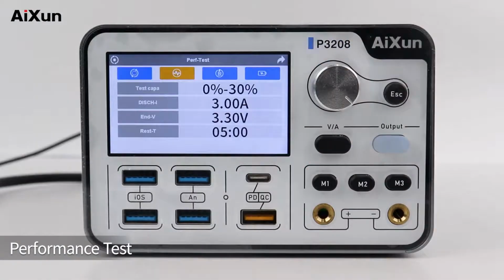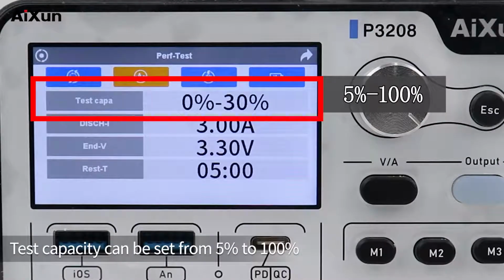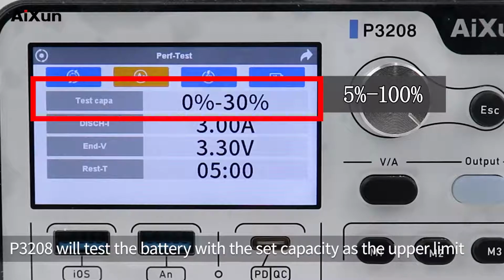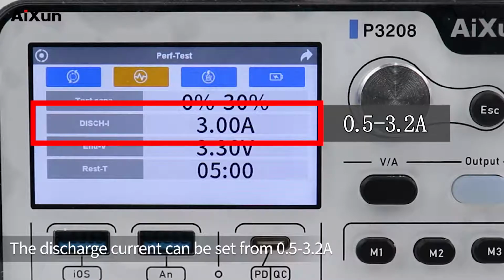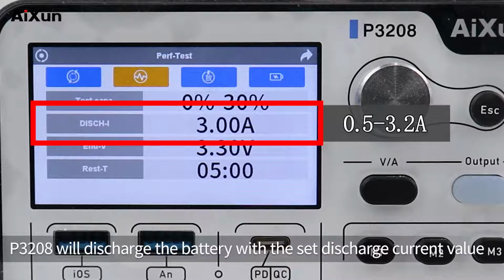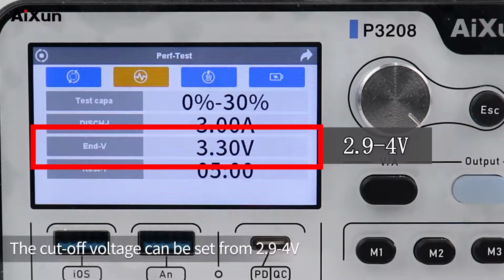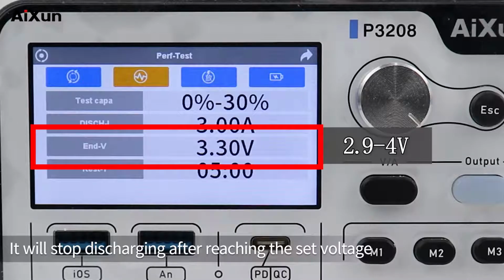Performance test. Test capacity can be set from 5% to 100%. P3208 will test the battery with the set capacity as the upper limit. The discharge current can be set from 0.5-3.2A. P3208 will discharge the battery with the set discharge current value. The cutoff voltage can be set from 2.9-4V. It will stop discharging after reaching the set voltage.